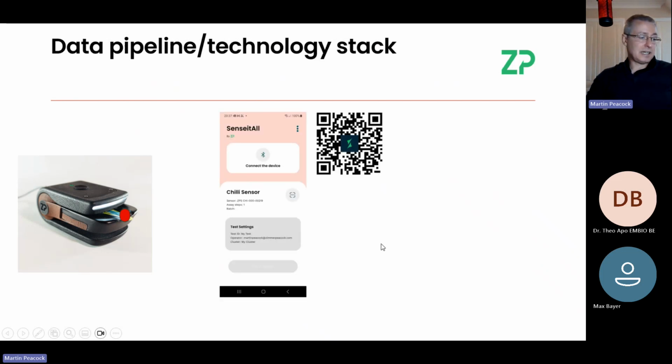When I did that test, I actually have a whole array of QR codes in front of me. So this system is not menu driven. It's actually QR code driven. The QR code tells the app what to do. The app runs the meter. The meter essentially energizes the sensor. On the sensor, there's the liquid sample. So we get some information, or data, out of that sample.